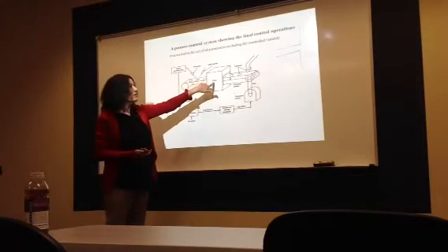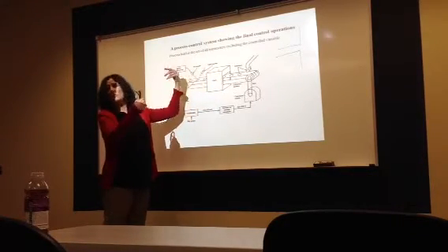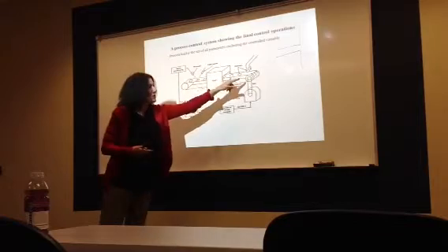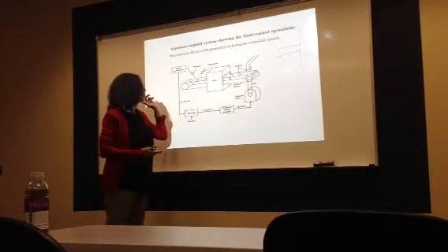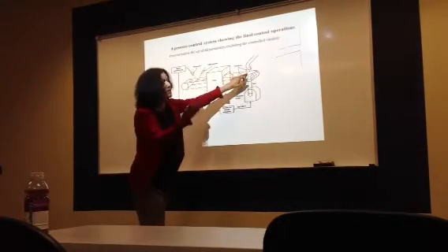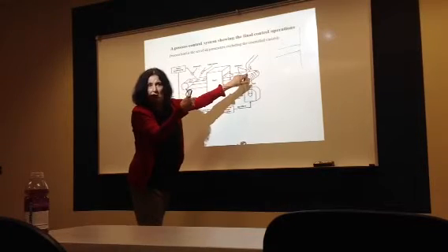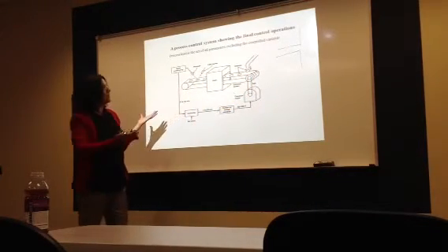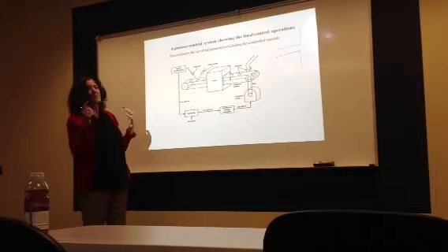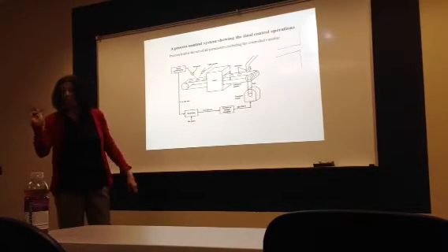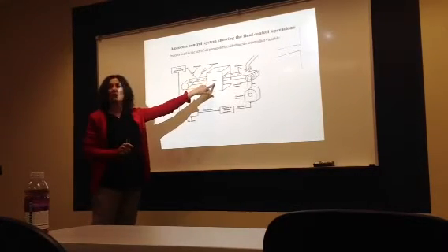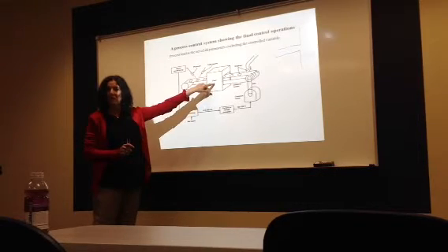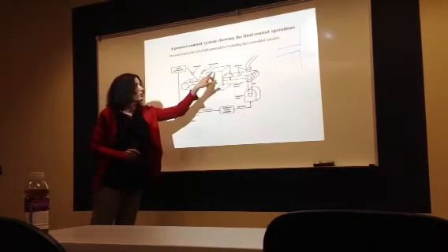We could control the temperature inside the oven, the temperature outside the oven, the conveyor speed, the extruder feed rate. So you could use multi-variable parameters, or you can choose one parameter. You say, okay, I'm going to control just the heat inside, or I'm going to control the motor speed.